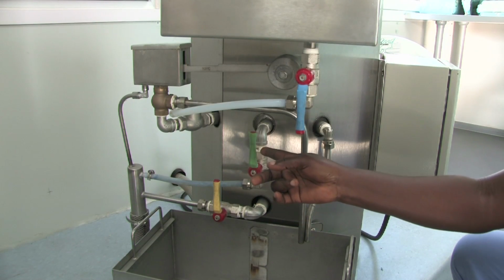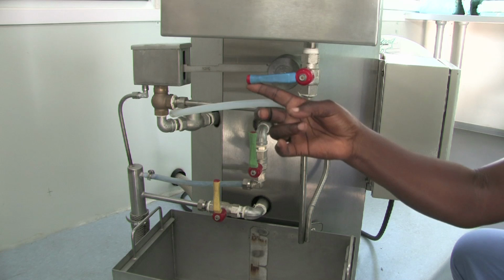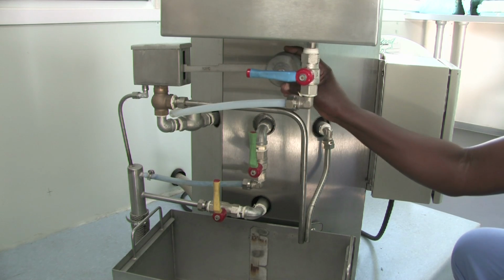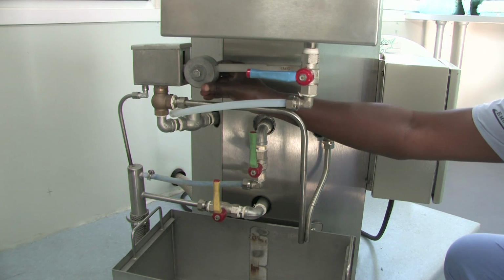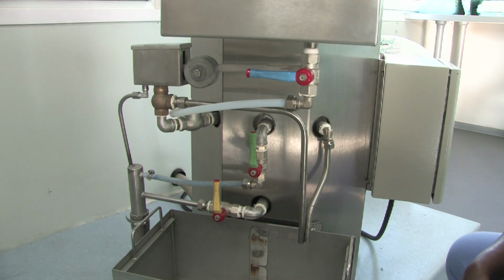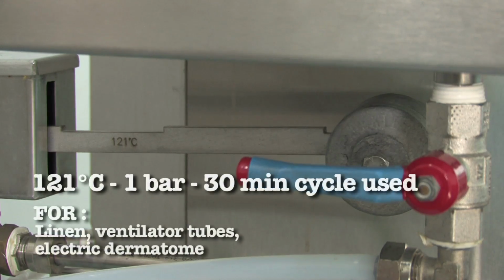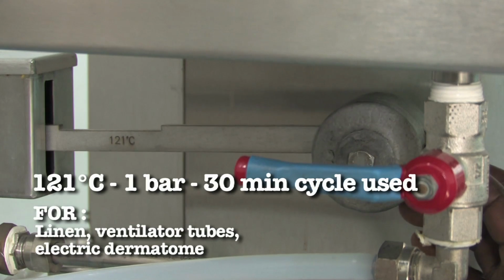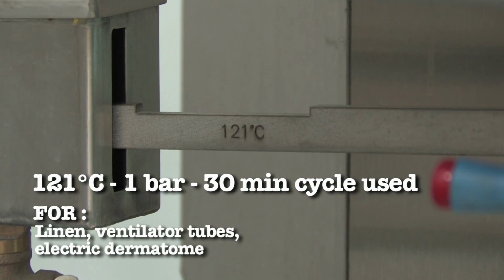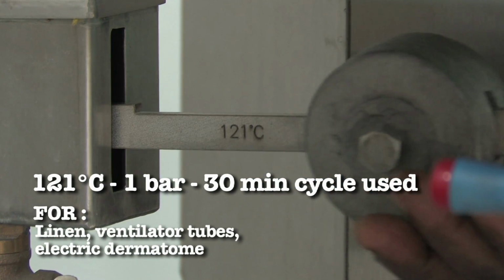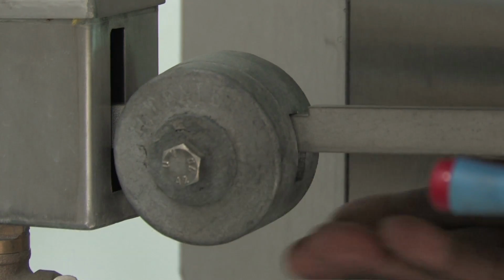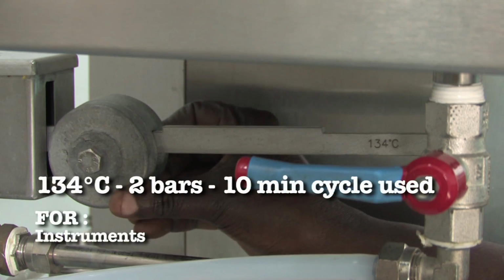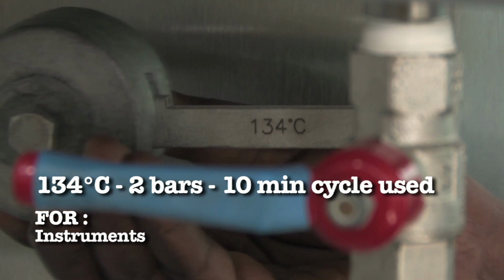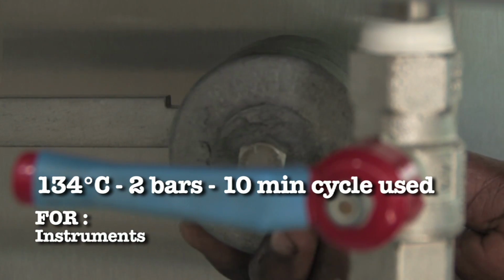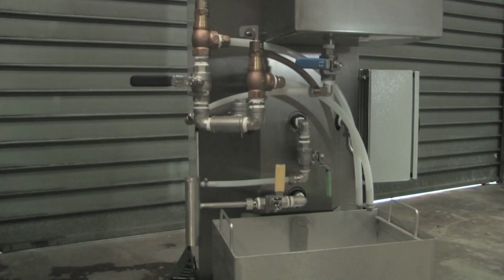(1) Choose the appropriate sterilization cycle for the load to be sterilized. Atmospheric pressure is considered 0 bars, so we're talking about relative pressure. At the first notch, the relative pressure inside the autoclave will reach 1 bar. The temperature of the saturated steam will therefore be 121 degrees Celsius. At the second notch, the pressure will reach 2 bars, or a saturated steam temperature of 134 degrees Celsius.